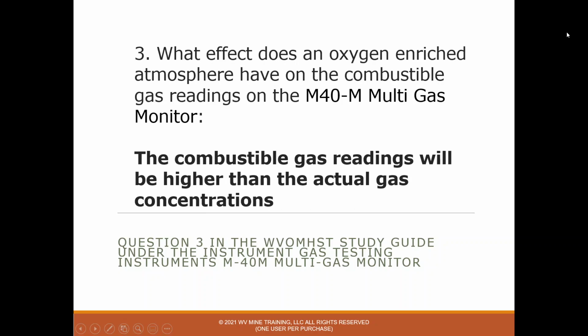Question 3, what effect does an oxygen-enriched atmosphere have on the combustible gas readings of the M40-M multi-gas monitor? So oxygen is higher than normal. So the answer is the combustible gas readings will be higher than the actual gas concentration. So if it asks this question with oxygen, if it's lower, your gas readings will be lower than what they actually are. If oxygen is higher than normal, your gas readings will be higher than what they actually are.